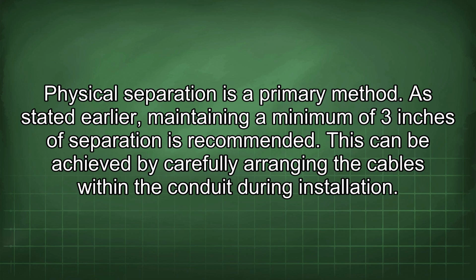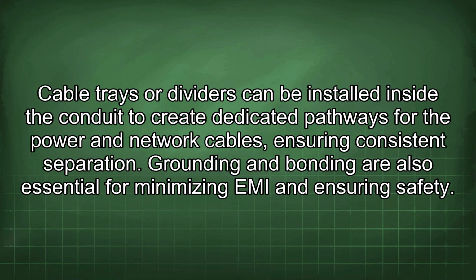Physical separation is a primary method. As stated earlier, maintaining a minimum of 3 inches of separation is recommended. This can be achieved by carefully arranging the cables within the conduit during installation. Cable trays or dividers can be installed inside the conduit to create dedicated pathways for the power and network cables, ensuring consistent separation. Grounding and bonding are also essential for minimizing EMI and ensuring safety.